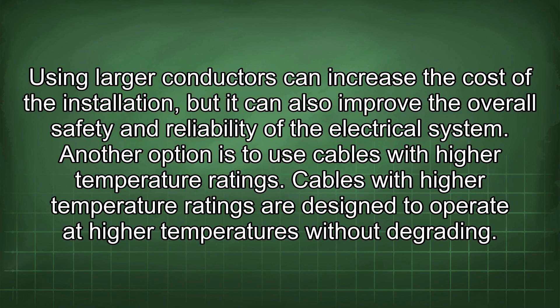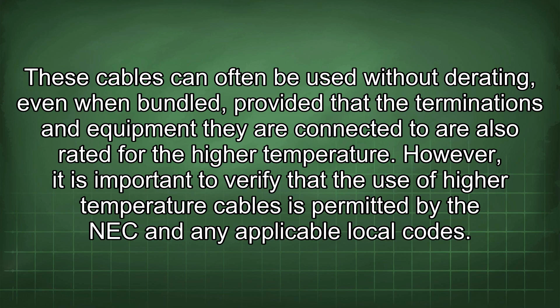Cables with higher temperature ratings are designed to operate at higher temperatures without degrading. These cables can often be used without derating, even when bundled, provided that the terminations and equipment they are connected to are also rated for the higher temperature. However, it is important to verify that the use of higher temperature cables is permitted by the NEC and any applicable local codes. In some situations, it may be possible to avoid bundling altogether by using a different wiring method.